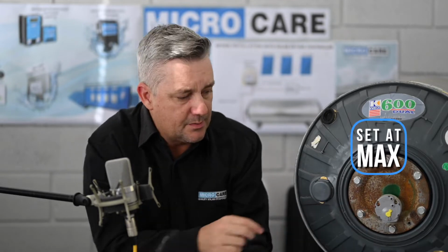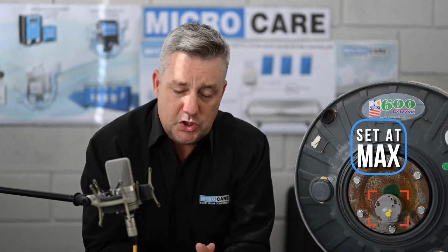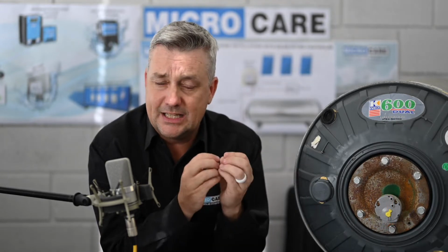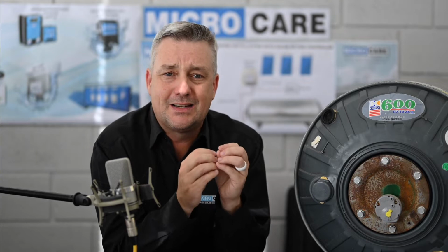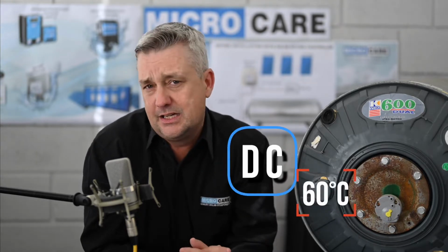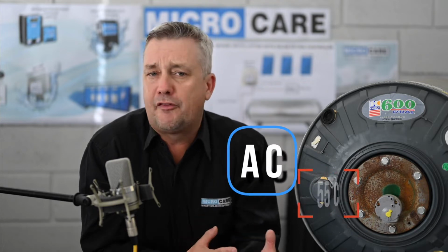People often ask, what temperature should I set the geyser at? It's very important that the thermostat on the back of the geyser is set to maximum, and that is a toggle over here which you would have seen earlier on our thermostat installation. So it's important that it's set to max, and find out from your client what temperature they would want. We would recommend on the DC side something like 60 degrees, and then on the AC something like 55.